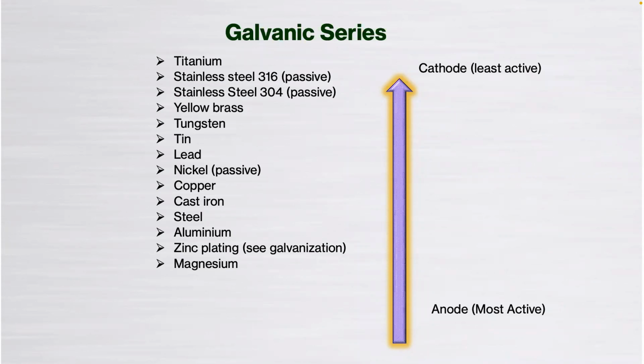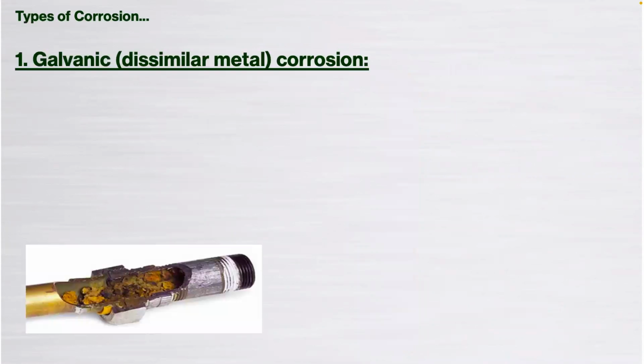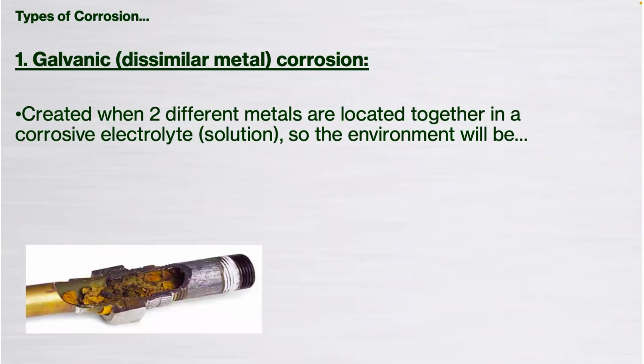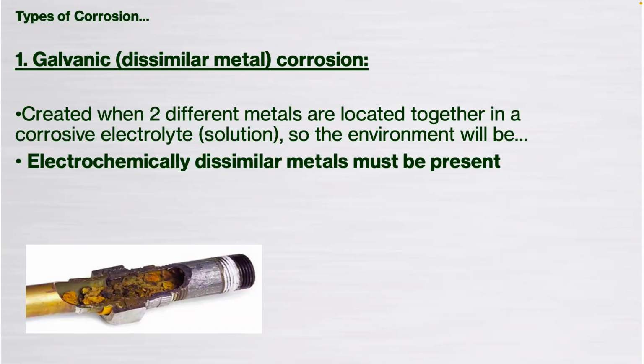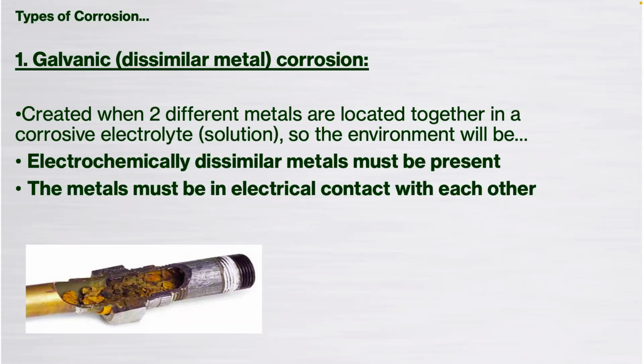So the next slide I'm going to show you sort of paints that picture ultimately. If we're looking to connect any pieces of metal that are dissimilar in any way, we need to ensure within any specification that the contractor uses appropriate jointing compounds or jointing couplings to prevent this from happening. But for us to have galvanic corrosion, we need those two different types of metals located together and then in an electrolytic solution, which is the water. So we need dissimilar metals. We need them to have electrical contact with each other.